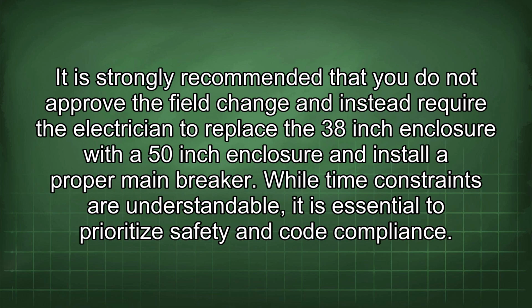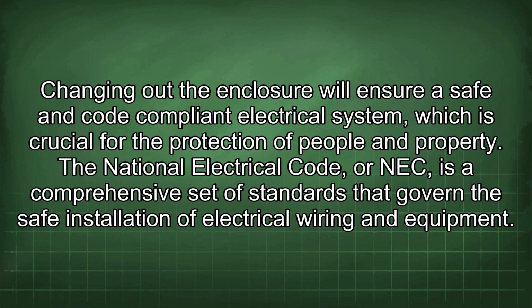It is strongly recommended that you do not approve the field change and instead require the electrician to replace the 38-inch enclosure with a 50-inch enclosure and install a proper main breaker. While time constraints are understandable, it is essential to prioritize safety and code compliance. Changing out the enclosure will ensure a safe and code-compliant electrical system, which is crucial for the protection of people and property.